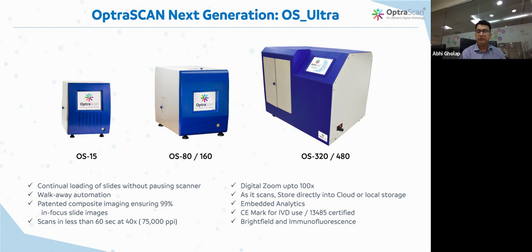In addition to the scanning, this also offers some composite imaging abilities, where you can see how the images are scanned and some of the areas which are not in focus because the cell stack has different focal planes. And we actually create an image called a composite image, where it picks up the pixels which are all in focus across the different Z levels. And instead of storing it as a Z stack, it can also store it as a composite image. So with such patented technologies, our scanning solution becomes more efficient and smarter when it comes to scanning the tissues or the cells.